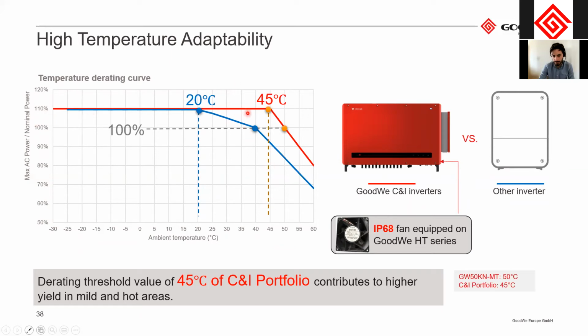Our whole C&I portfolio could operate at up to 100%, up to 45 degrees Celsius, and our MT inverter, up to 45 degrees Celsius, operates at 110% of the nominal power, and then it starts to derate to not overheat, but still at 50 degrees Celsius, it operates at 100% of the nominal power.